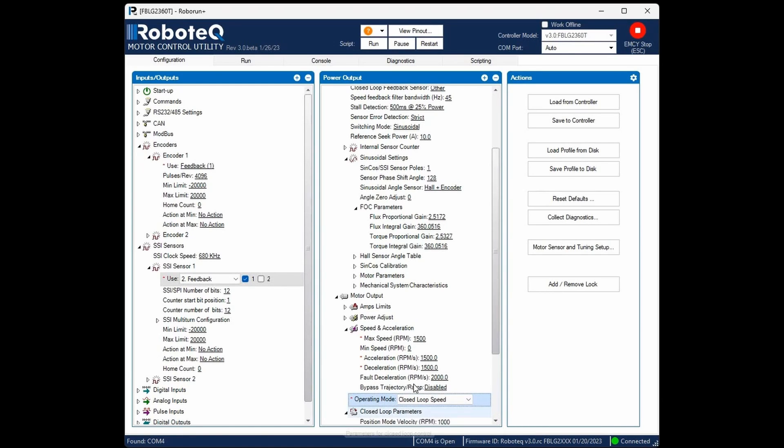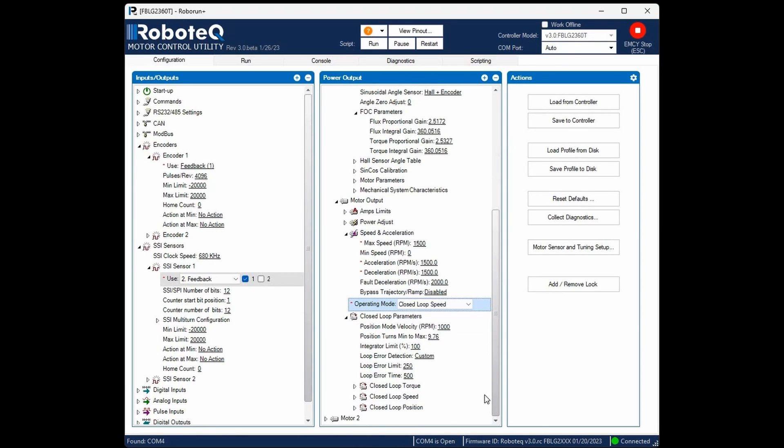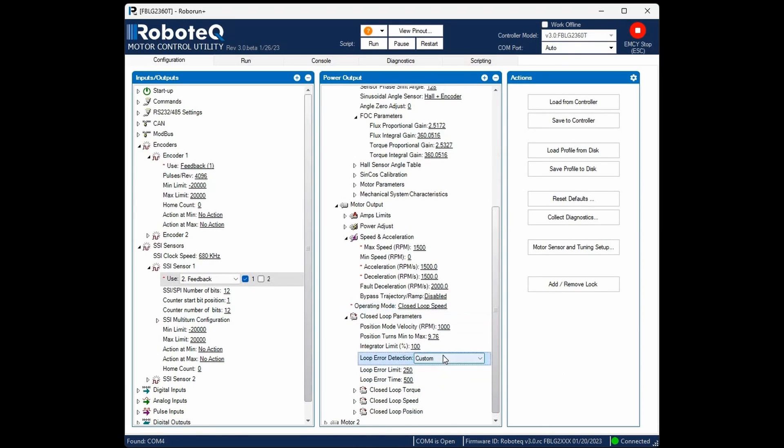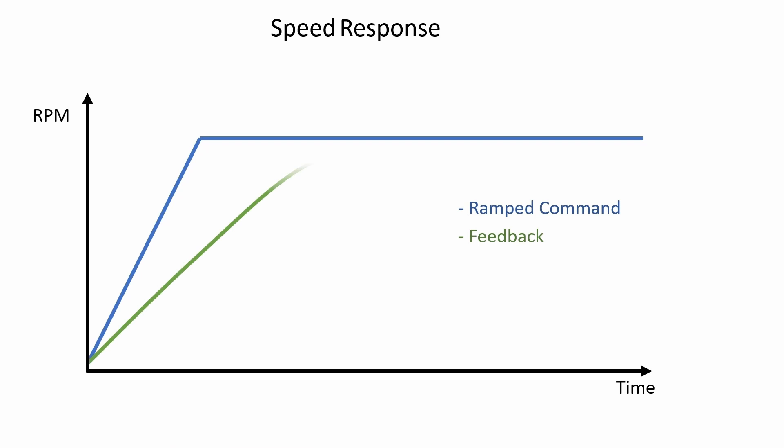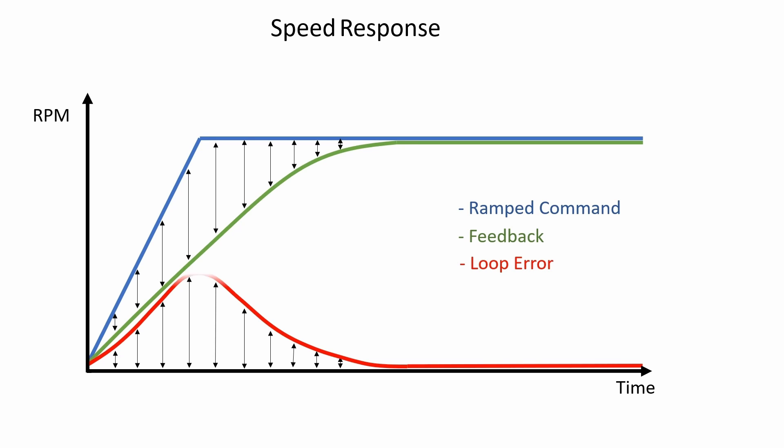Temporarily disable the closed loop error detection. This error detection will be triggered if the motor response is slower than expected, which could indicate a motor failure or an overload condition. At this stage, where the motor is not yet properly tuned, this feature should not be taken into account.